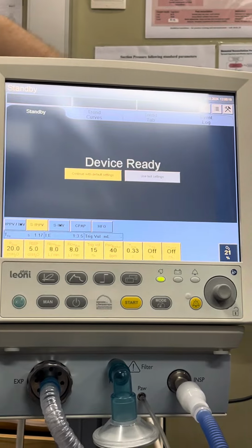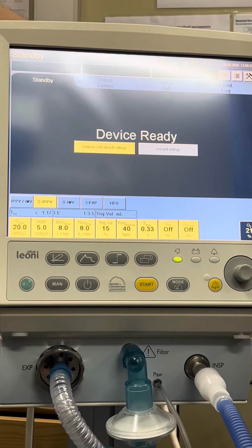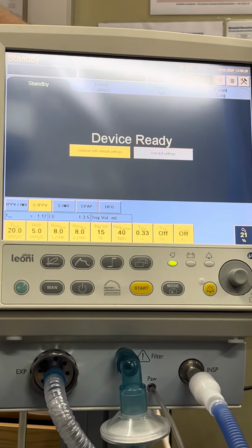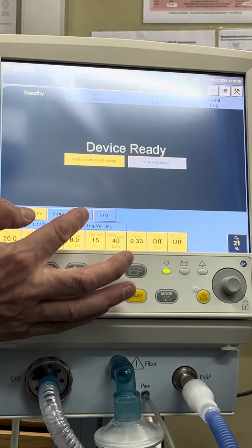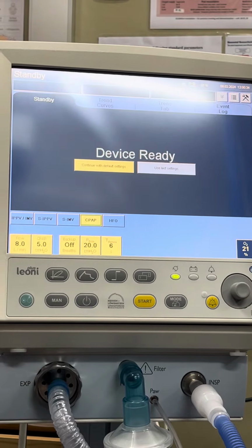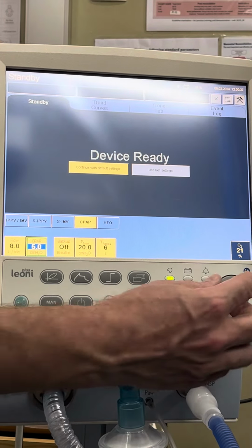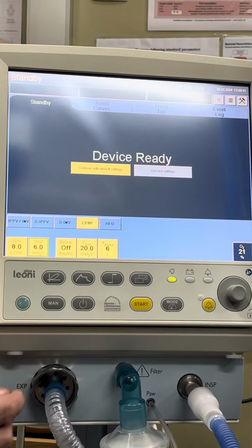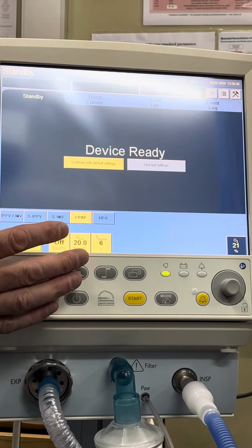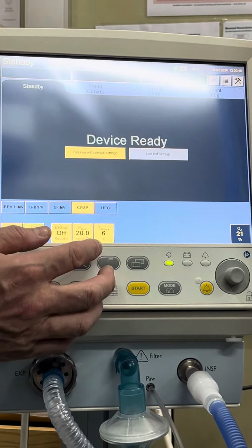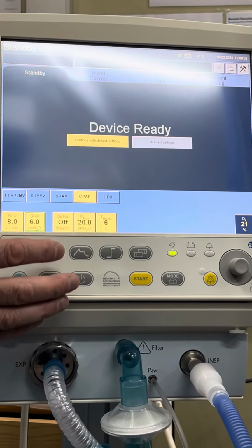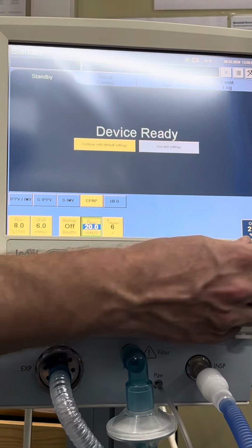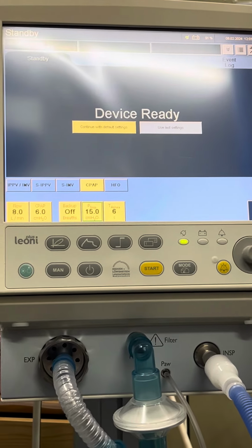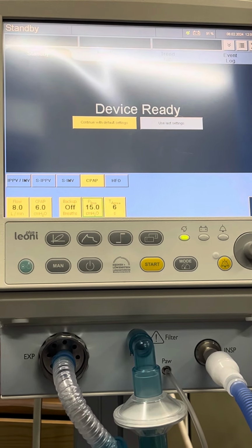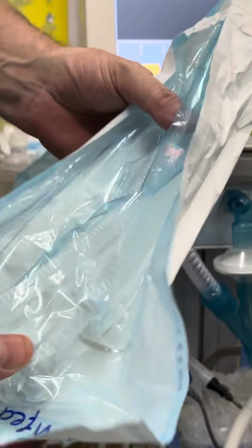Now, this is the SIPPV setting. Before I do anything now, I just shortly demonstrate to you the CPAP setting. There's a flow of 8, PEEP of 5, put the PEEP on 6. The backup is now turned off, so nothing will happen when the backup is not on, even if there's a P maximum set of, let's say, 15. If the backup is not on, it will only give the normal CPAP, and then you need a different tube set, and it looks like this: small prong, small mask.